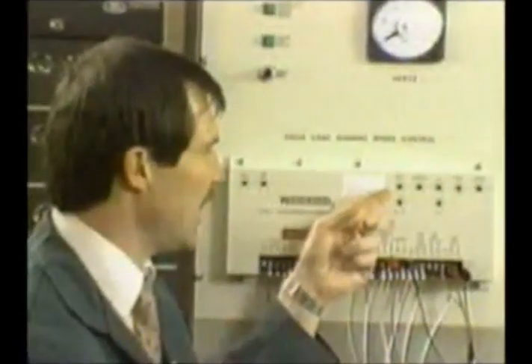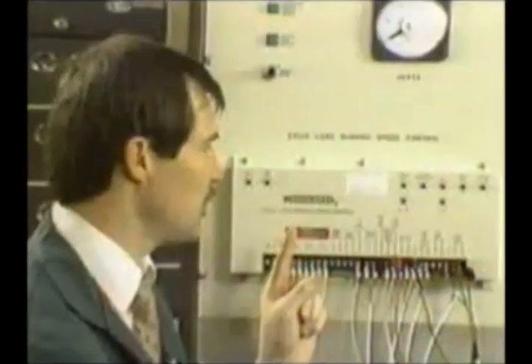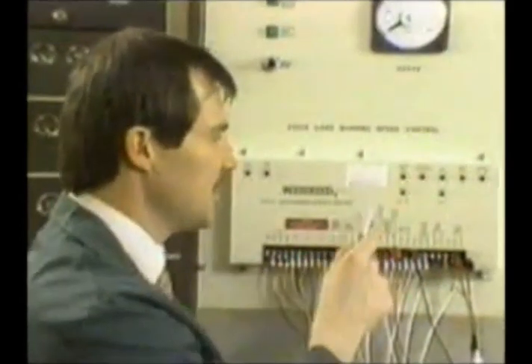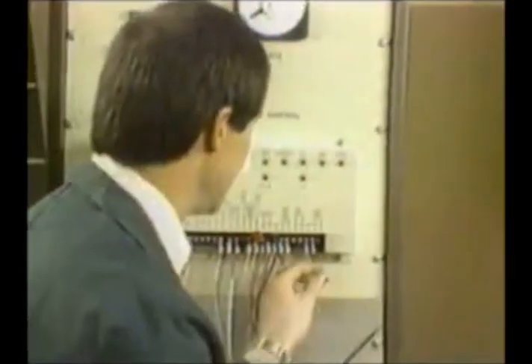And you have to remember, the idle potentiometer is just a one-turn pot where you have a 10-turn rated speed pot. So it's going to be harder to set up your idle speed to where it's barely creeping up in voltage. So anyhow, now I have my idle speed set for just above 3100 hertz. I'm going to disconnect my function generator. I need to reconnect my speed signal.